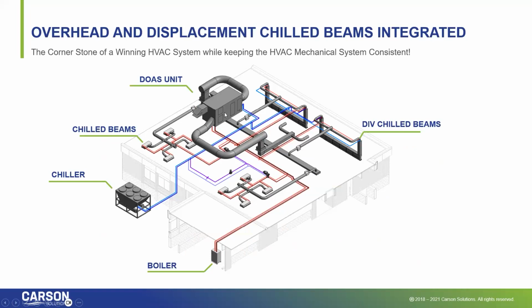So that is a more elaborate schematic that you see on the screen. Here is your 100% outside air unit delivering fresh air down the corridor, feeding fresh air, primary air, to these displacement chill beams in the typical classrooms for a school example, and then maybe delivering 100% outside air to overhead chill beams in, say, libraries, conference rooms, office spaces. And then you see oftentimes a chiller and a boiler integrated to produce the respective water medium supply.